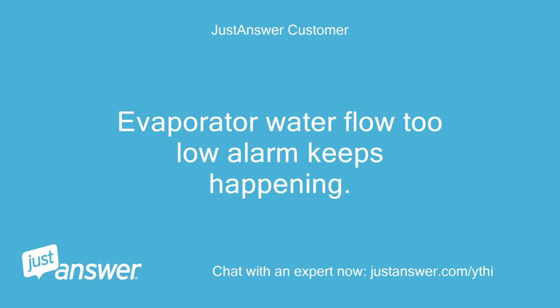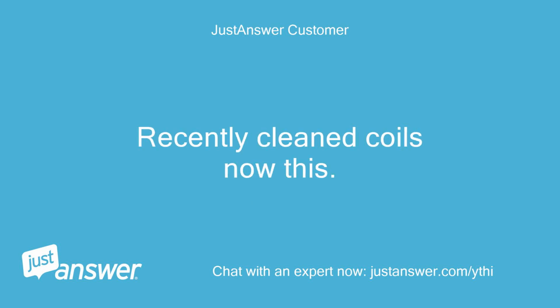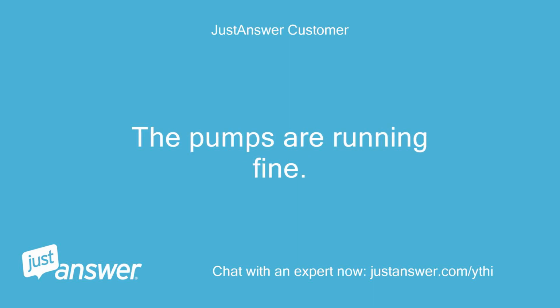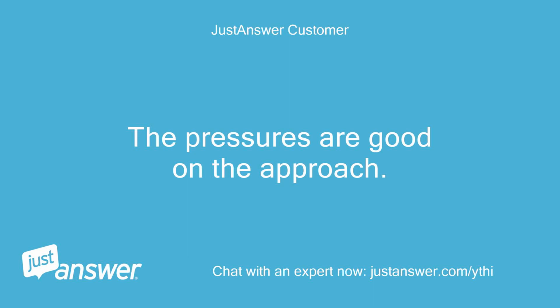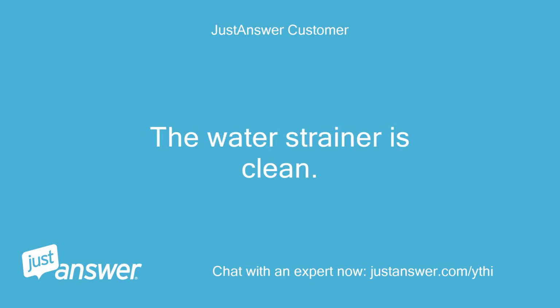Evaporator water flow too low alarm keeps happening. Recently cleaned coils, now this. The pumps are running fine. The pressures are good on the approach. The water strainer is clean.